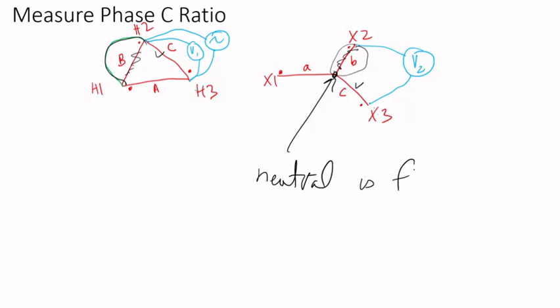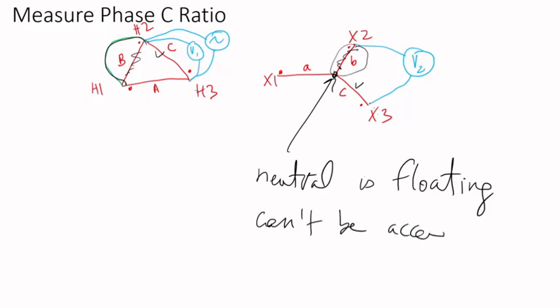The neutral, sometimes people say it's floating, which means it's inside. So it can't be accessed. You have no access to it. In other words, you cannot connect the voltmeter to it. So this is another method you can measure the turns ratio.